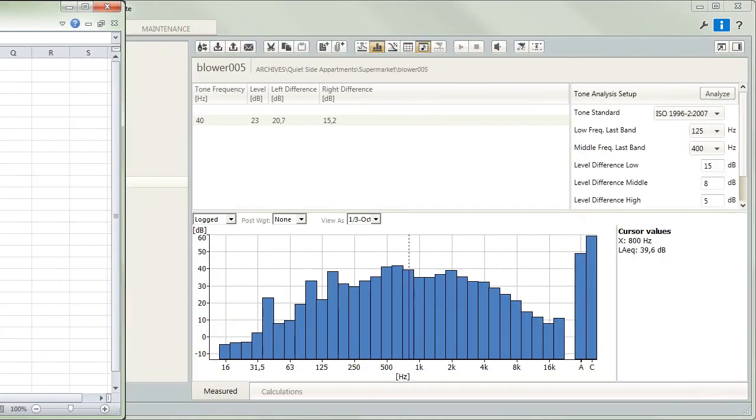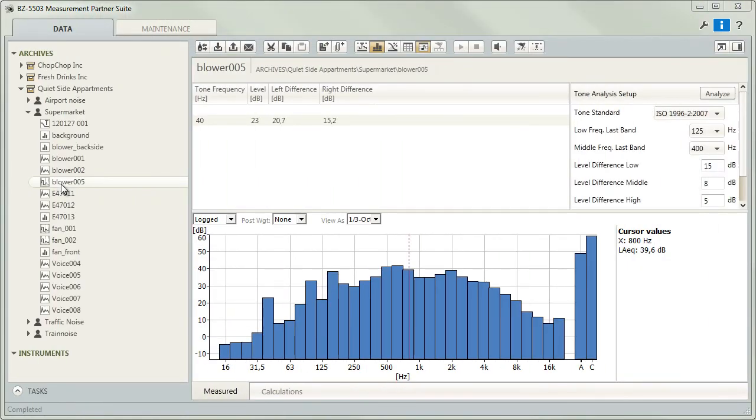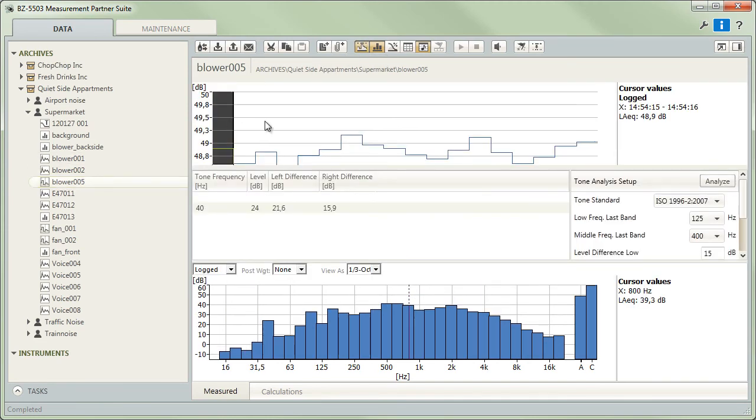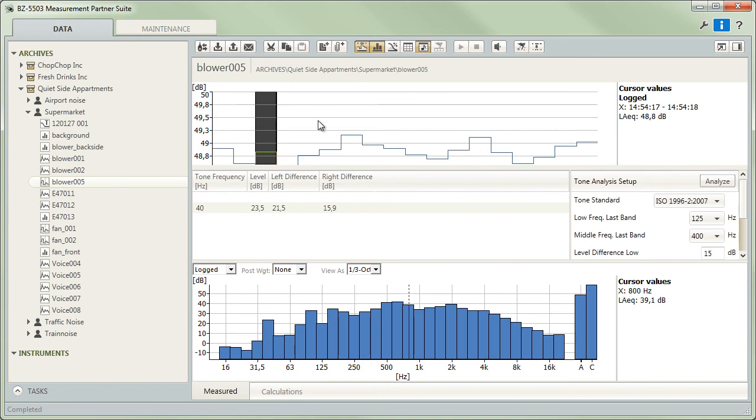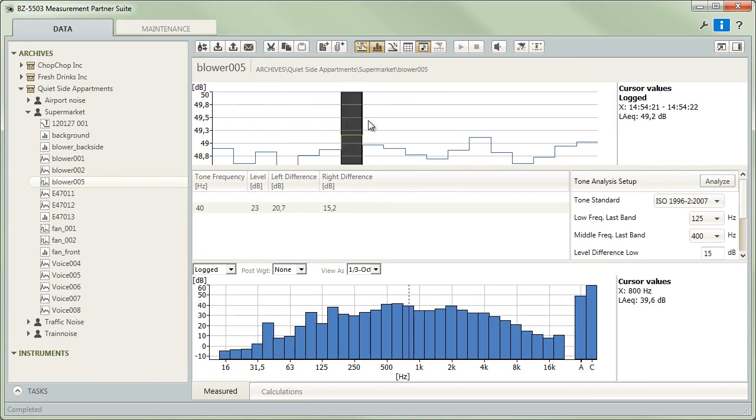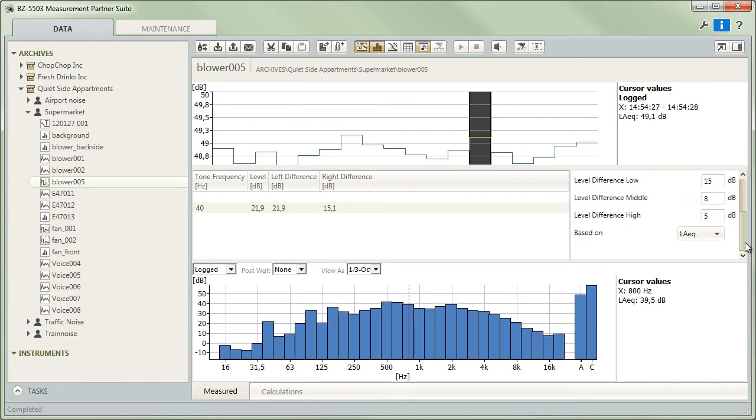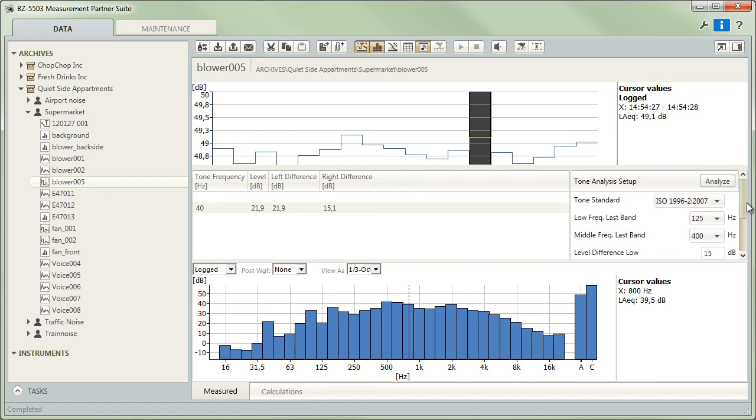Tone assessments of third octave spectra can be carried out on dedicated frequency analysis projects or selected spectral data from logging measurements. Again, you will get the results immediately in a table, with Measurement Partner listing all frequency bands in the spectrum for which tone criteria are exceeded.